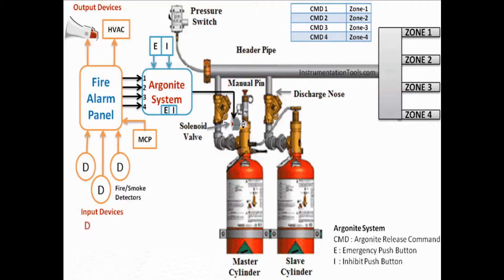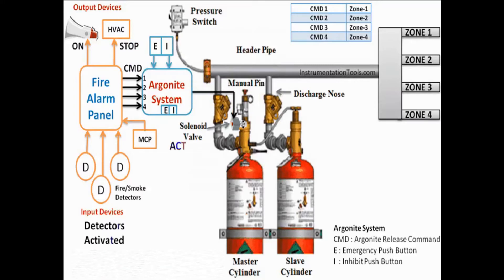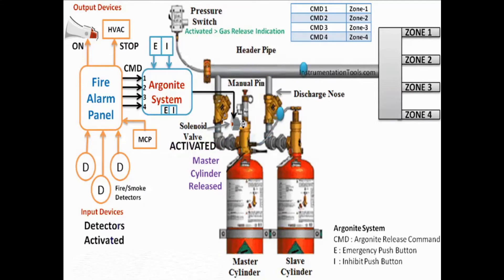Argonite System Operation: When any fire incident happens, fire and smoke detectors will be activated. These detectors give a signal to the fire alarm panel. The fire alarm panel activates the hooter and stops the HVAC unit. Also, the fire alarm panel sends an argonite release command to the argonite system.